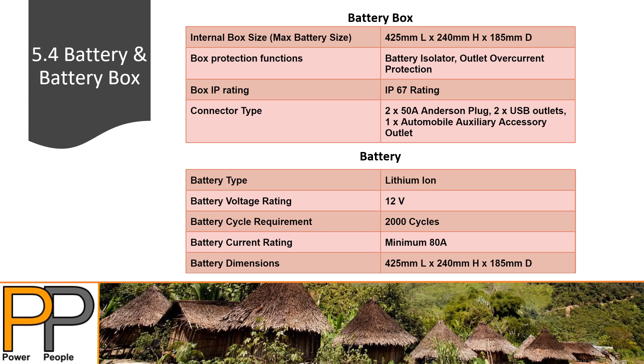The battery itself, we've asked for lithium ion, 12 volts. It has to have a requirement of 2000 cycles. This is to meet the minimum lifespan of the system, and also we need an amp hour rating of 80 amp hours, that is, for the battery current. And the battery dimensions, obviously, align with that of the box.